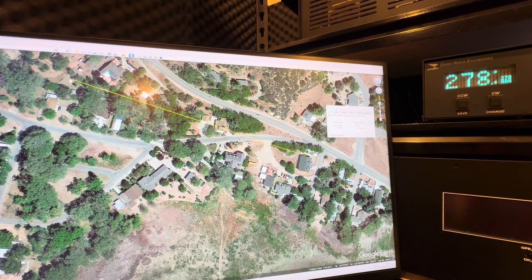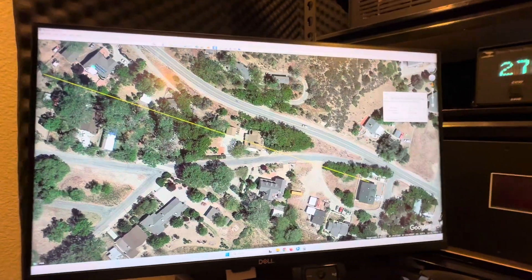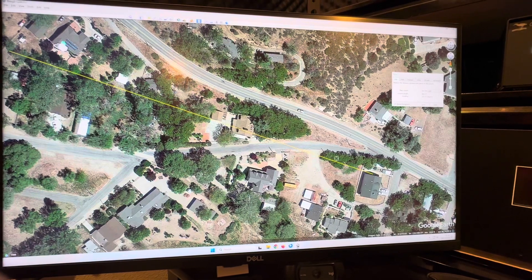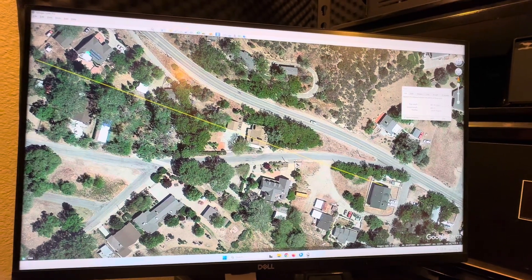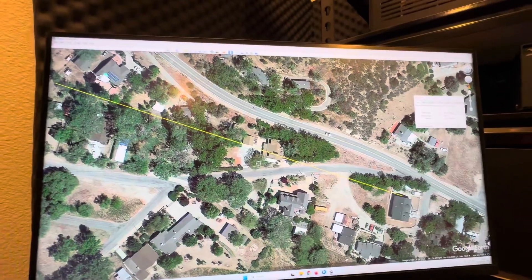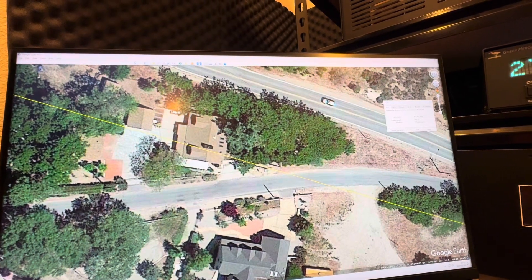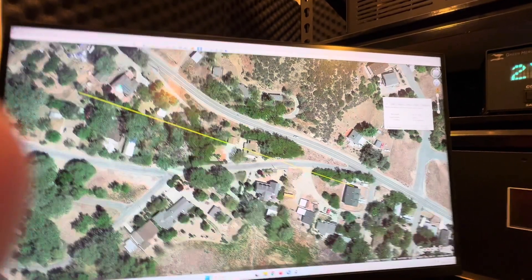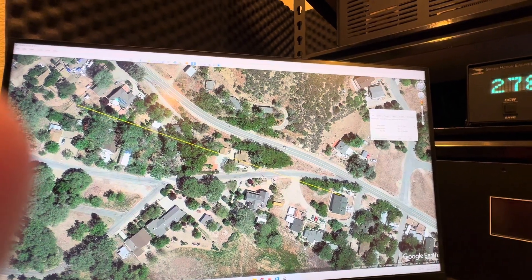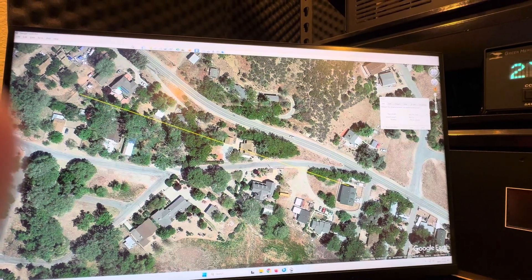At 270 degrees there. I already walked the road. I have a Yaesu VX7 radio, which I can put on AM on both 2 meters and 440, and I have an aero 2-meter 440 satellite and handheld antenna. I walked this direction and on AM I was able to kind of pinpoint between two different poles. Then going to UHF at 436 MHz on AM, I was able to pinpoint to one specific pole right here. There's a pole right there that has some lightning arrestors on it. I then used an MFJ parabolic ultrasonic dish and was able to identify the specific component — a lightning arrestor on the north side of the transformer phases is what's causing all this noise.